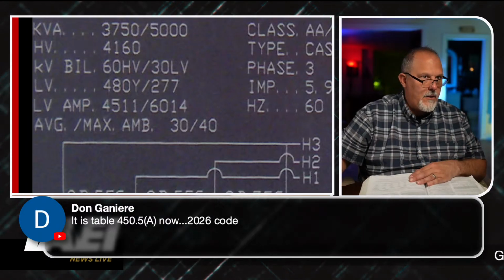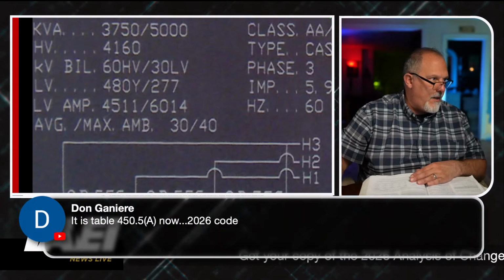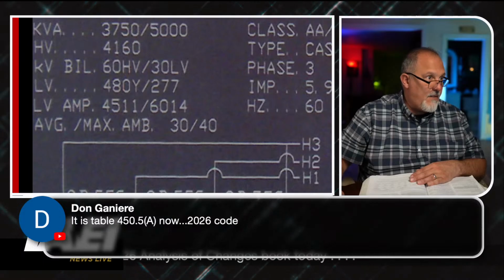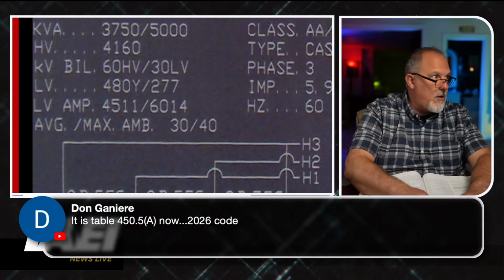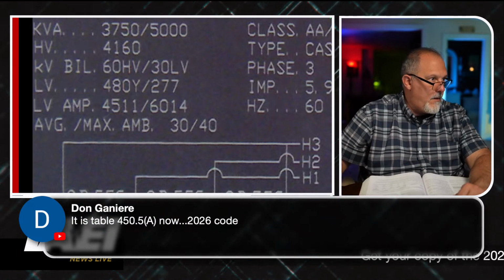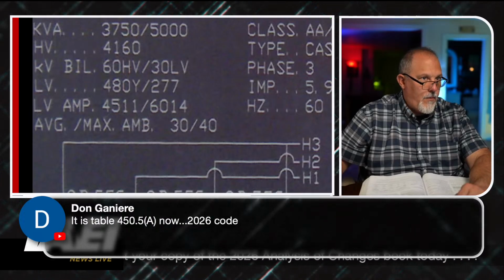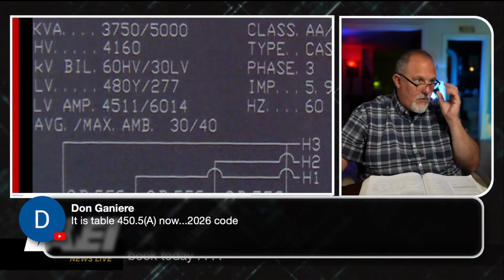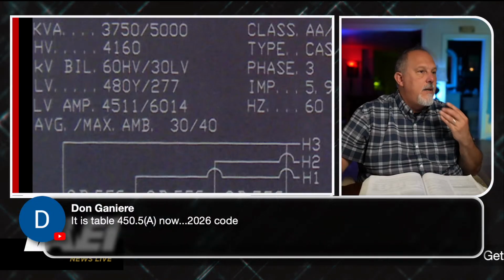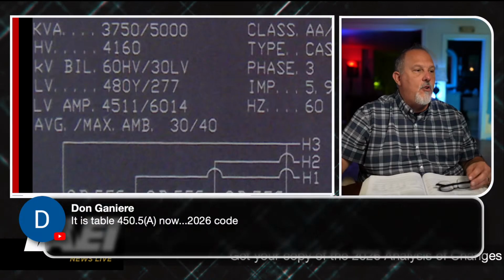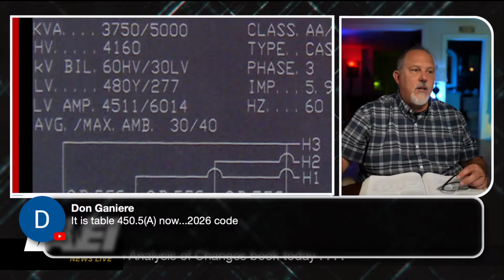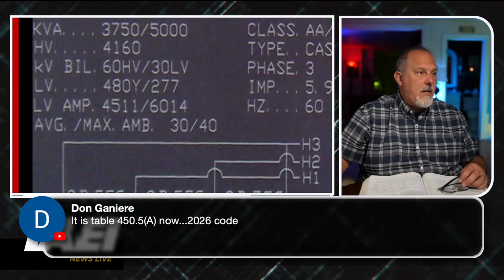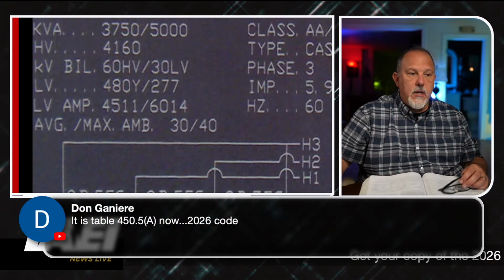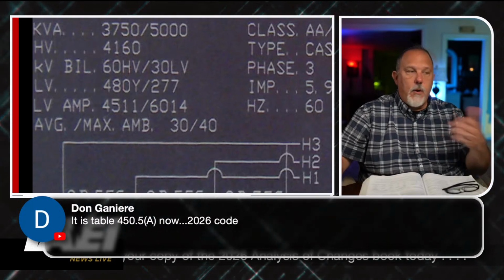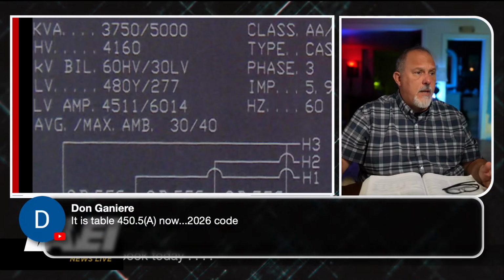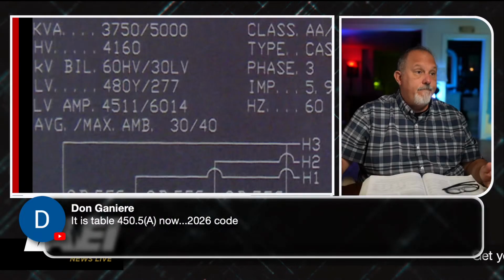In fact, you know what? The other thing we can do, I'm going to go to 450 in NFPA LiNK and search for the word fan to see if there's anything in 450 that uses that terminology. Ventilation shall dispose of transformer full load heat losses without creating temperature rise. So that's ventilation. In 450.11, they talk about ventilation openings, ducts, marking, the required clearances. That's all about clearances. 450.45 is ventilation openings. 450.41 is talking about location. It's all about ventilation for around a transformer. I just typed in fan and it's got a lot of hits.